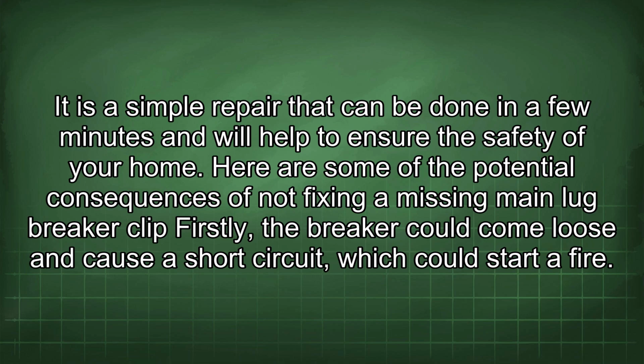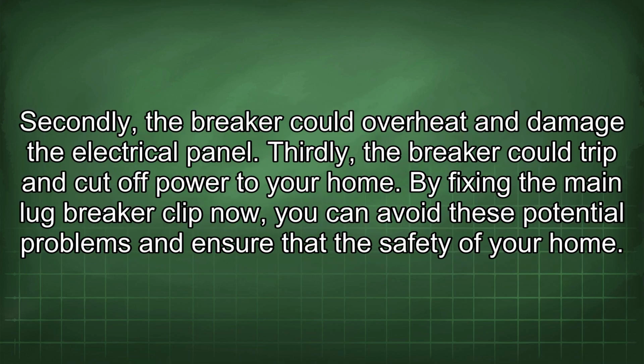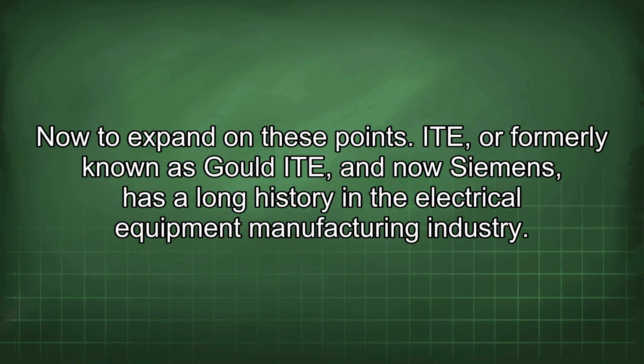It is a simple repair that can be done in a few minutes and will help to ensure the safety of your home. Here are some of the potential consequences of not fixing a missing main lug breaker clip. Firstly, the breaker could come loose and cause a short circuit, which could start a fire. Secondly, the breaker could overheat and damage the electrical panel. Thirdly, the breaker could trip and cut off power to your home. By fixing the main lug breaker clip now, you can avoid these potential problems and ensure the safety of your home. Now to expand on these points.